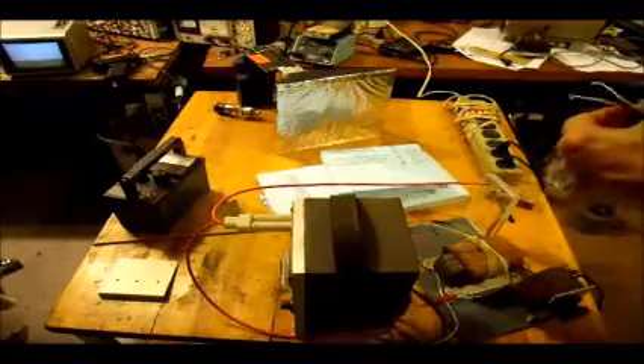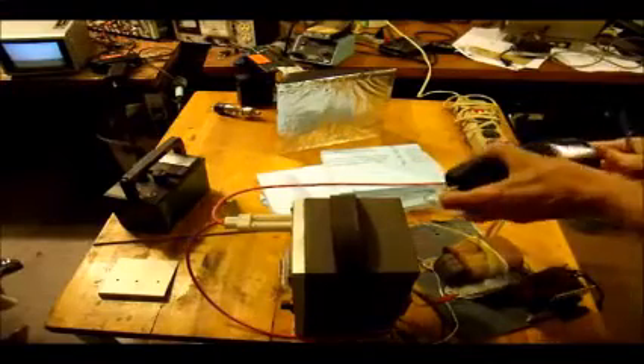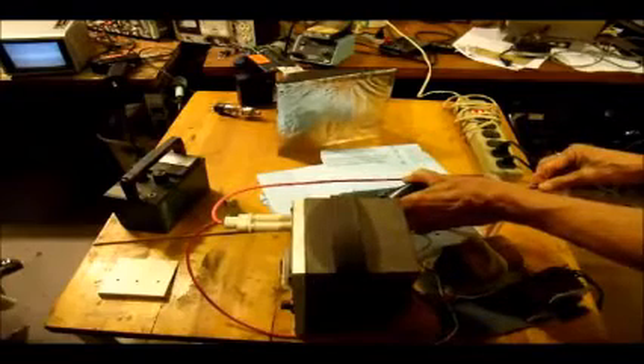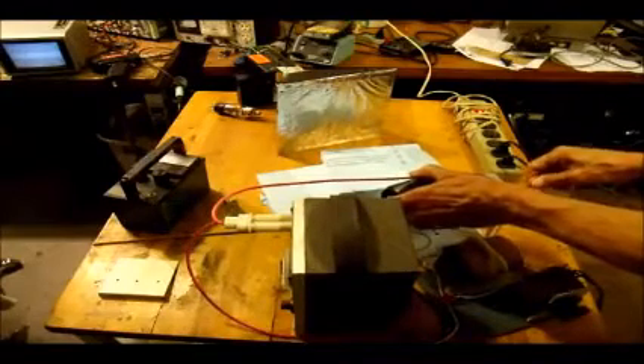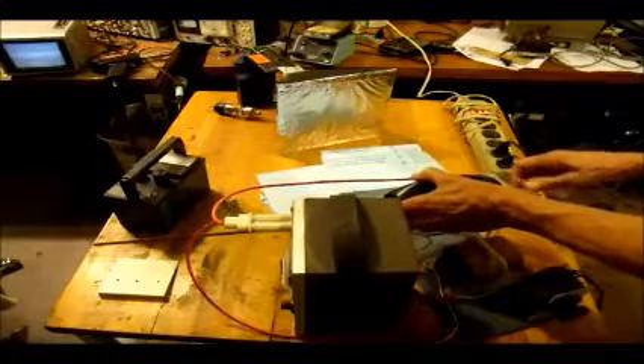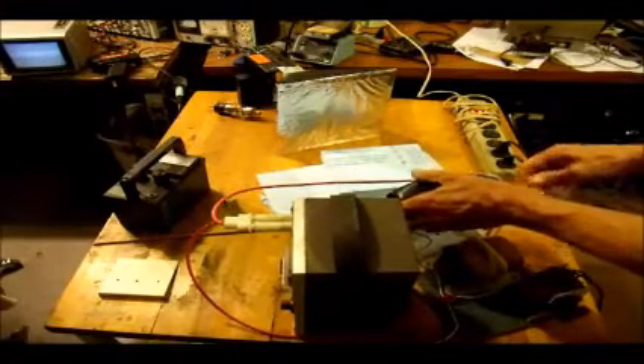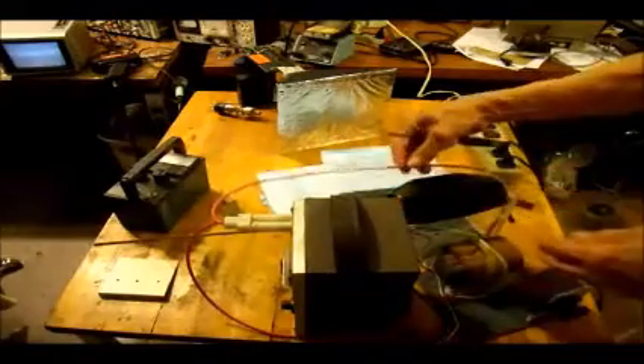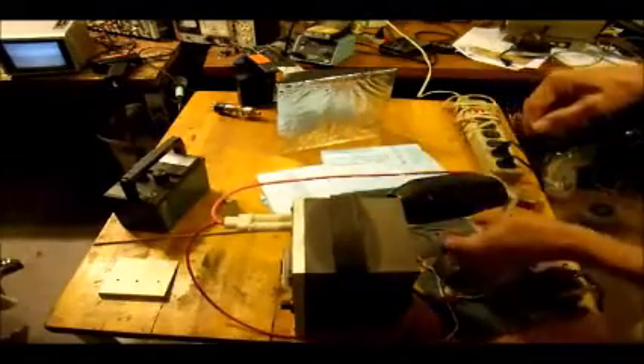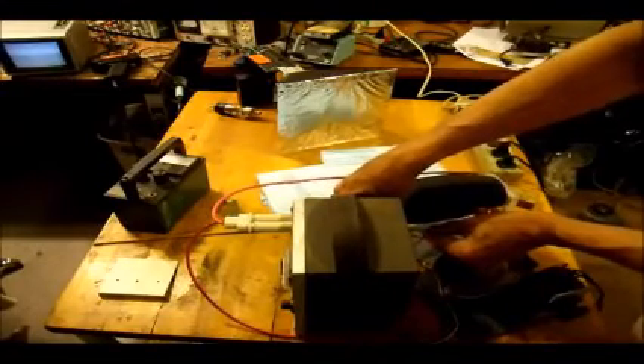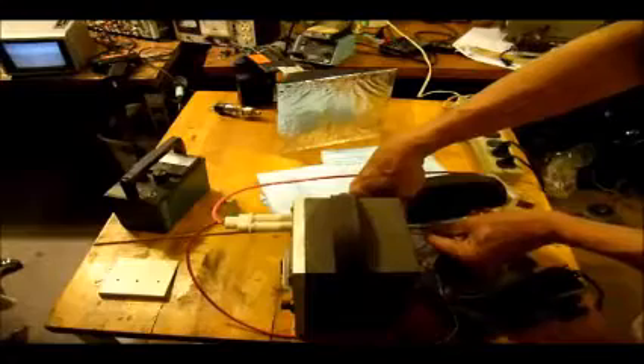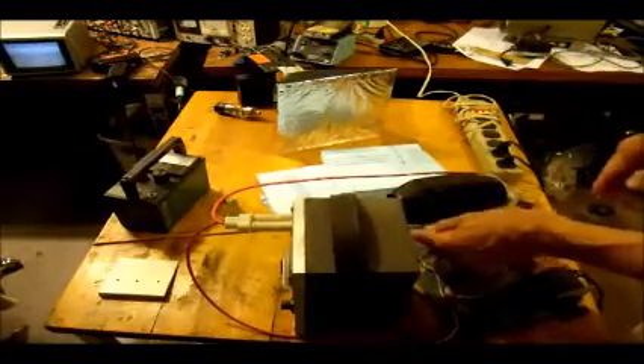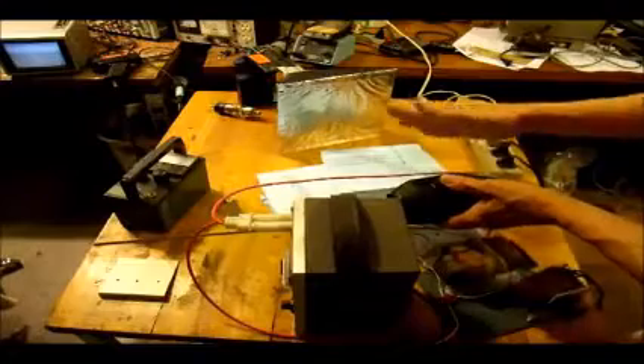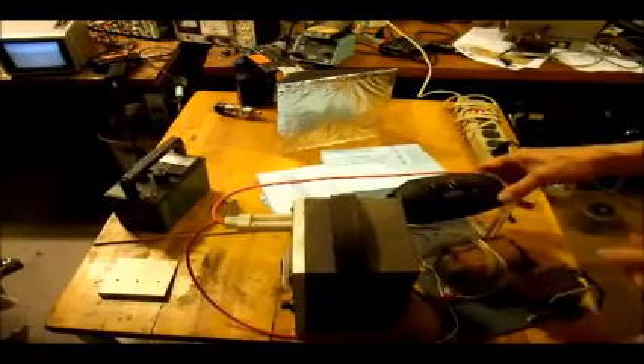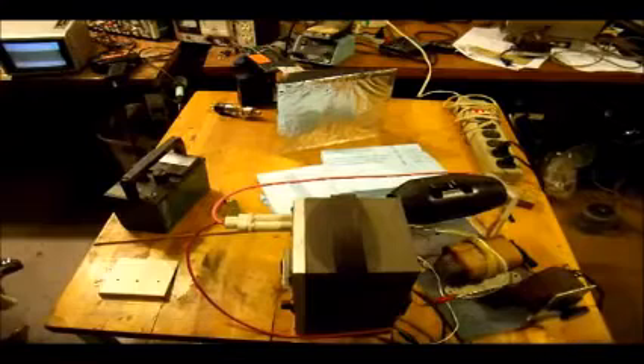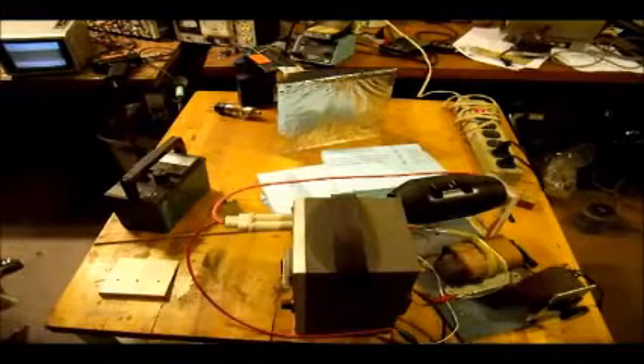So what we'll do is stick that in there. And we've got a screw here that goes up in there and catches that screw in the end. Get it lined up. Okay. And we'll get our high voltage wire hooked to it. And our filament wires hook up just with these little quick connects. They did that very nicely in the X-ray machine, so that you just pull the transformer loose and the little quick connects come right out. Okay, we're going to aim that right off into the fluoroscope. Okay, and that's our setup.